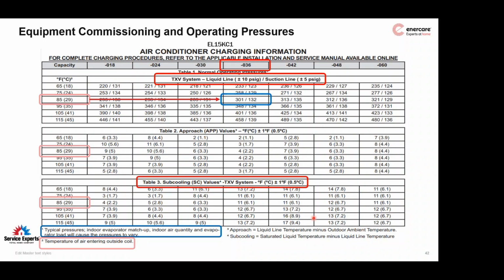If you're getting these pressures, or somewhere really close, there's a good chance your charge is going to be correct. But Lennox likes to validate further and give you the opportunity to check through approach, which is your temperature entering the outdoor unit versus your pipe temperature. If you have a difference of 3 to 5 degrees, or basically they're giving you 4 degrees, again, your charge is probably correct. If you have some differential, you might have to remove or add refrigerant depending on what you find.